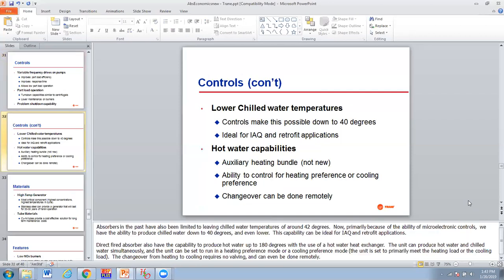Low chilled water temperature. Traditionally, about 42 degrees was as low as the absorber could go. Now, primarily because of microprocessor, microelectronic controls, we can produce chilled water down to 40 or even lower. This capability can be good for indoor air quality and retrofit applications.